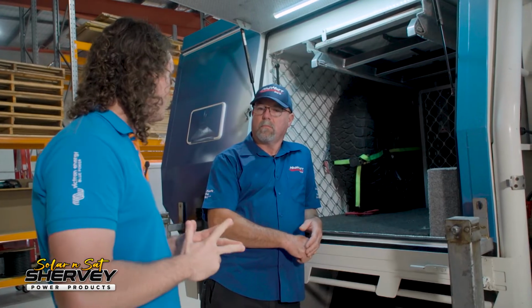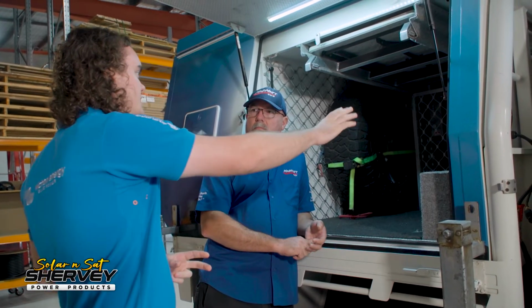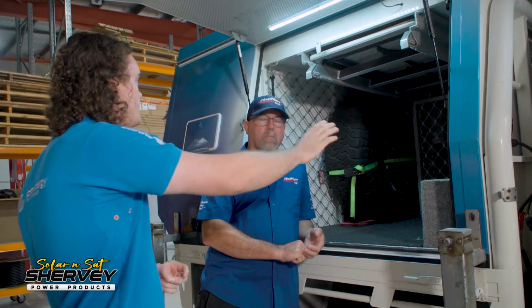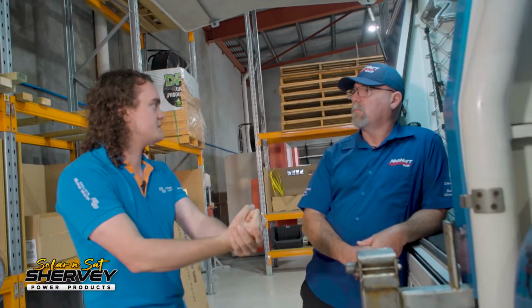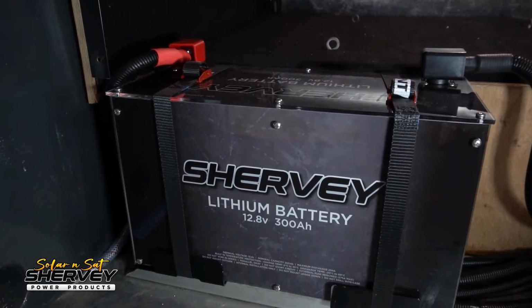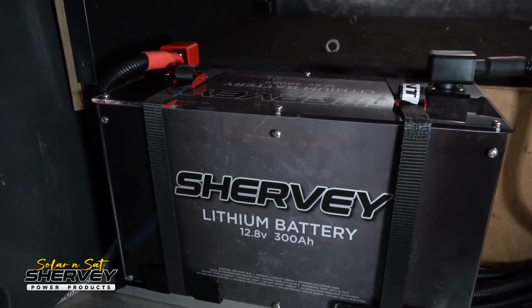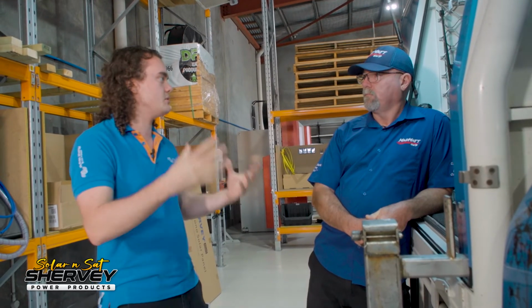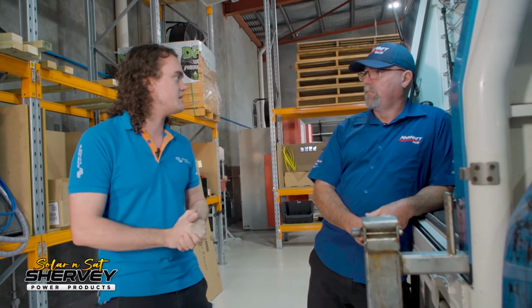A lot of people go, oh, lithium, it's lightweight, has more capacity, lasts longer. That's all true and important, but on a job like this, it's not actually the reason we do it. The main reason is a lithium battery can discharge without damaging the cells and keeping its design life reasonable, pretty much 1-to-1 ratio wise. So if you have a 200 amp hour lithium battery, you can normally discharge it at 200 amps. If you have a 300 amp hour lithium battery, you can normally discharge it at 300 amps, providing the internals, the BMS, the bus bars, all that sort of stuff's up to the task.